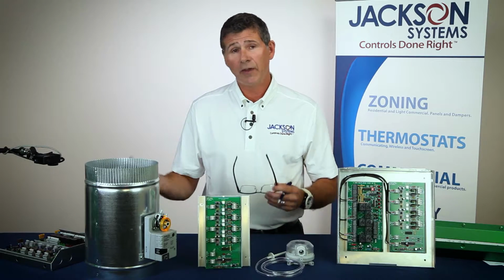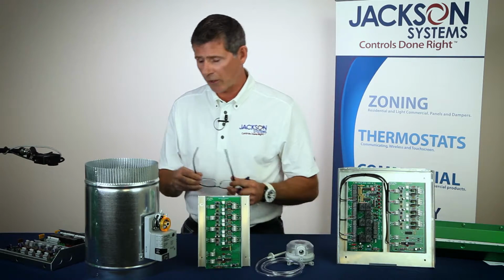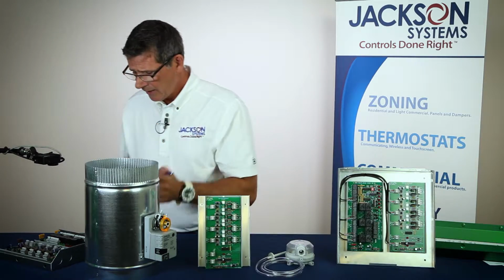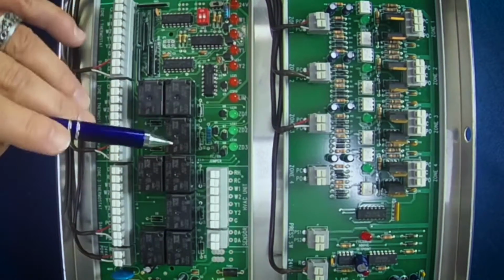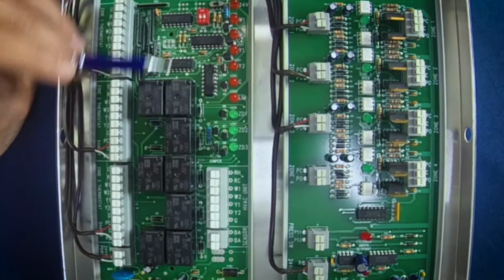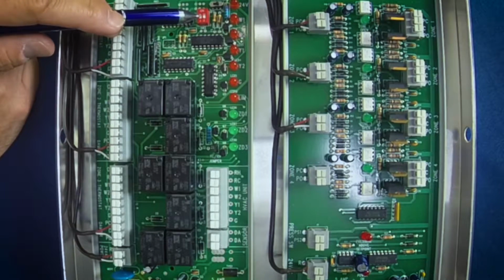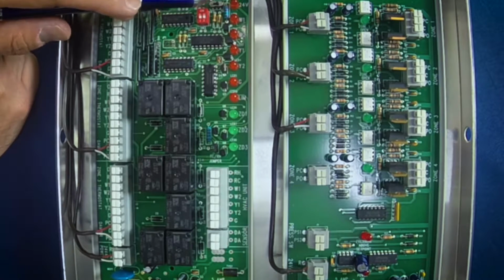So in this event, even though we're not bypassing air, you're still going to want to go ahead and install that. And then finally, again, your discharge air sensor down here. And of course, with our multi-stage system, we've got some switches here that allow you to go ahead and set your high limit on your discharge air sensor, and of course our purge option here as well for you.